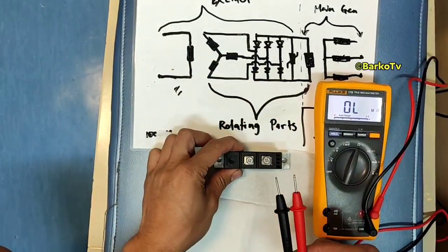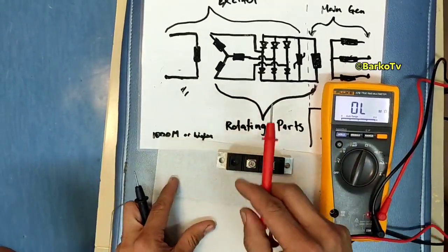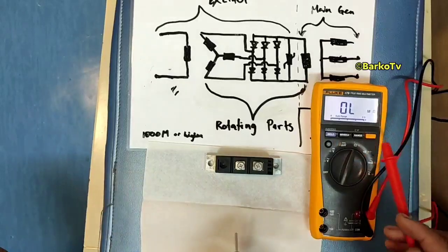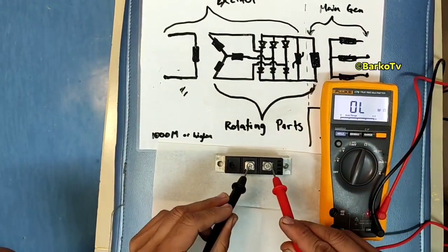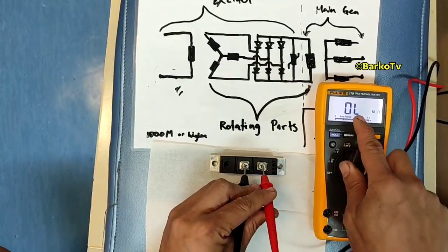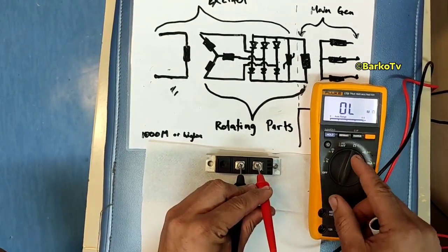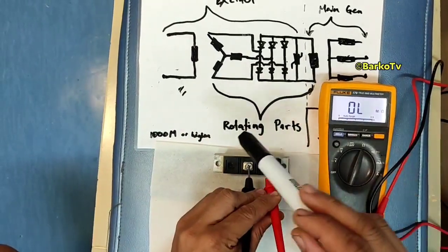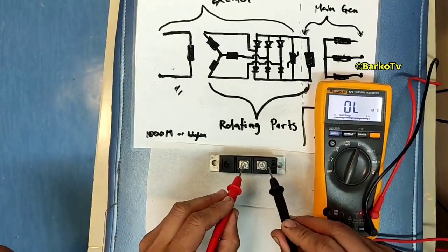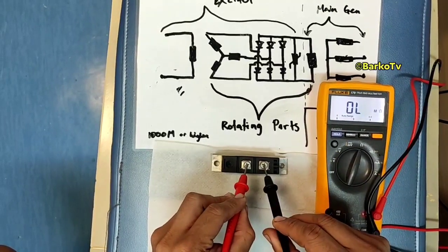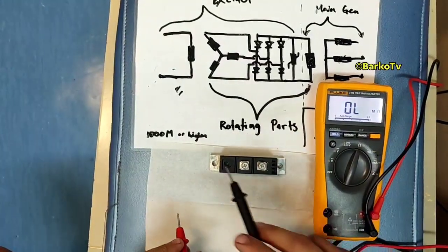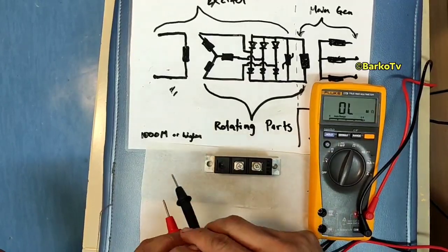In the varistor, the better or the good varistor reading is 1000 meg ohms or higher going to infinity. As you can see it's blinking, it's blinking, it means that is higher than 1000 meg. That is our reading.